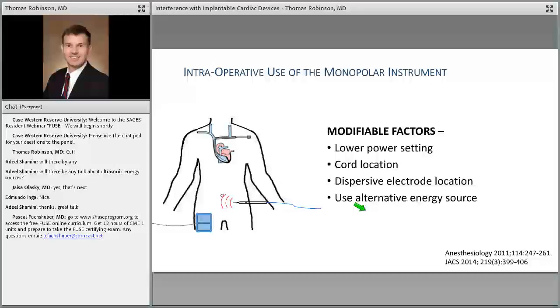And this is my last slide here, just to review the modifiable factors that you can do to minimize electromagnetic interference on the cardiac rhythm management device. So number one, you can lower the power setting. The cord location should be from the foot of the bed, and the cord location should never be draped across the chest. The dispersive electrode location, you should always put the dispersive electrode so that the current vector goes away from the device, so it doesn't go through the cardiac rhythm management device. Or you can use an alternative energy source, and the common ones would be the bipolar or the ultrasonic.